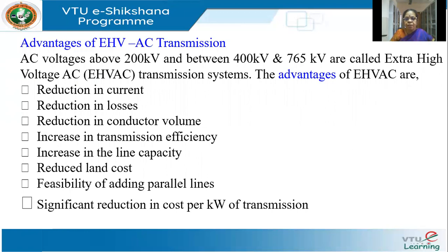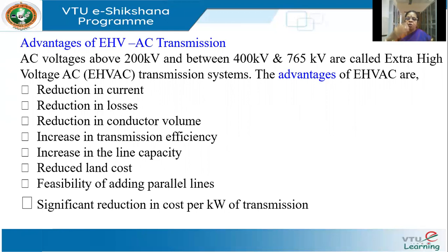The advantages of EHV AC — voltages between 400 to 765 kV — are the same as we saw for high voltage in general: more reduction in current and losses, reduction in conductor volume, increase in transmission efficiency, reduced land cost, increase in line capacity, feasibility of adding parallel lines, and significant reduction in cost per kilowatt of transmission. The conductor cost comes down, efficiency improves, land cost comes down, and installation cost comes down.